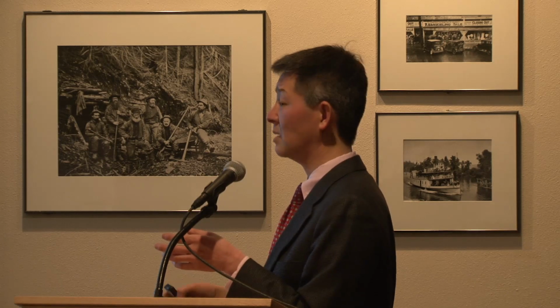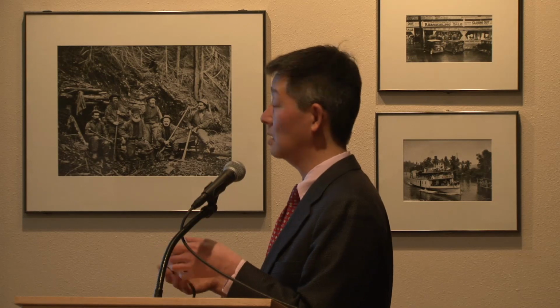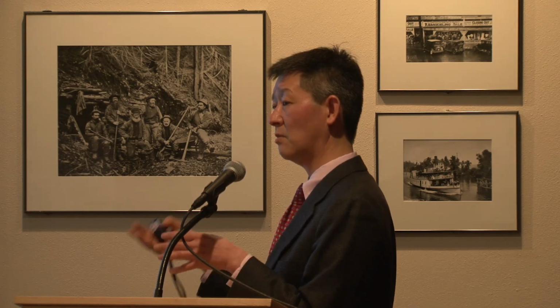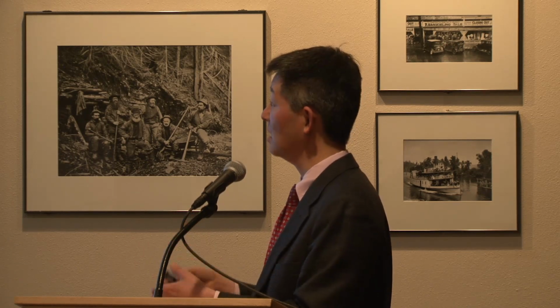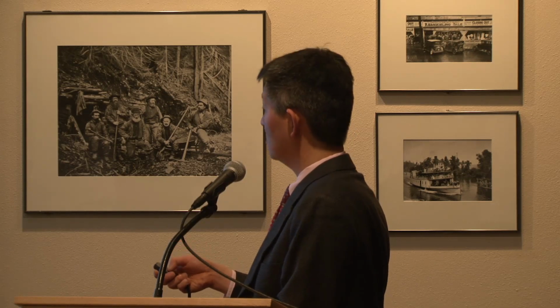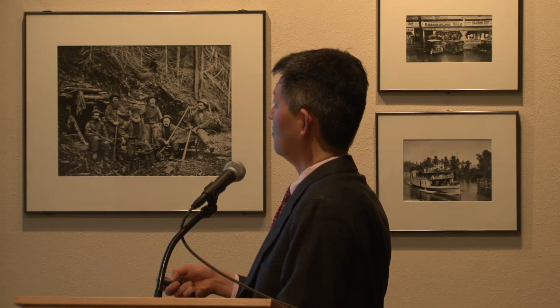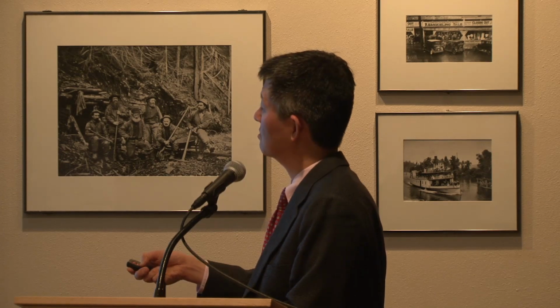If you don't have the backup generators, you don't have the capacity to take the decay heat cooling. So then you also have what you call a loss of heat sink. You've lost your capacity to take care of the decay heat. So in 60 days, we're having to do something that we never had any plans to do. We're going to install improvised heat exchangers to still take away the decay heat. So that's this first bullet.